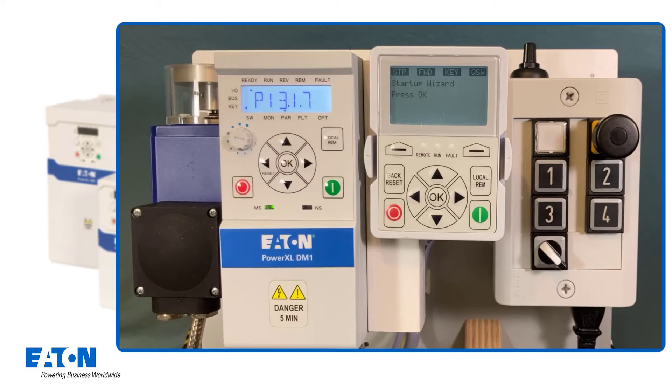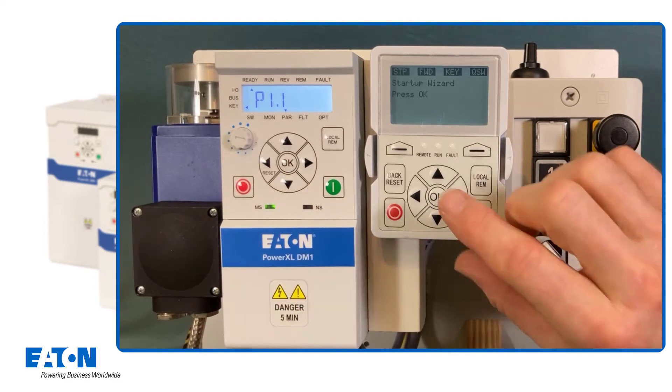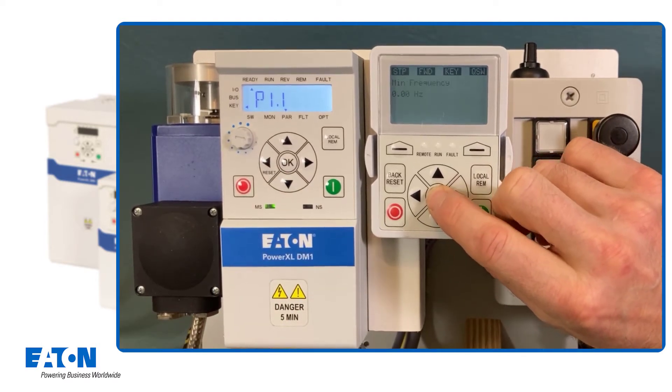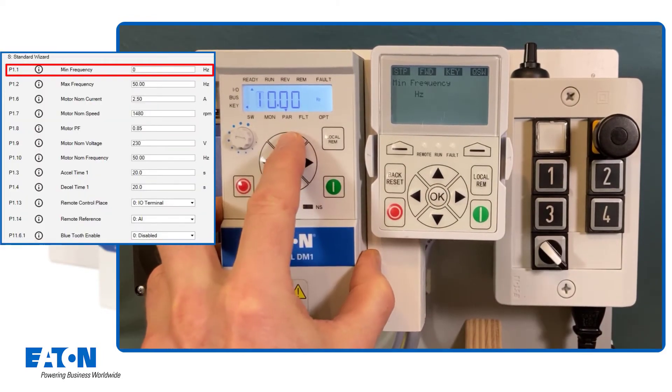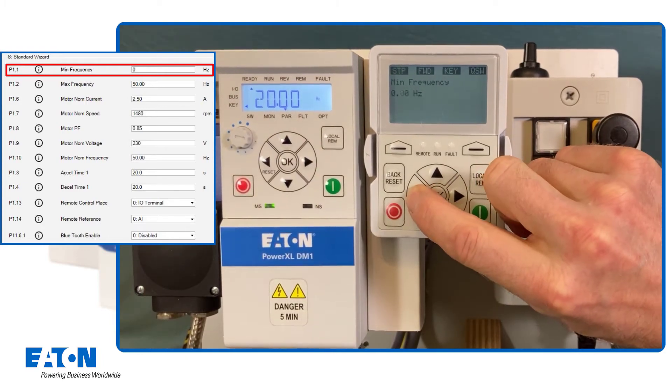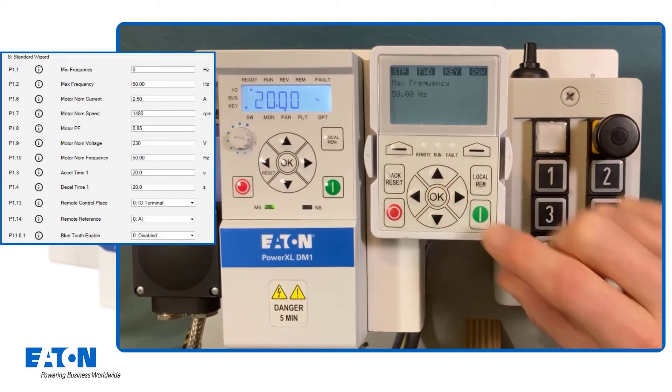On the internal keypad, the first parameter is displayed directly. On the external keypad, the start-up wizard is started with OK. First, you are asked whether the set parameters should be protected against unauthorized changes with a password. In our example, no password is used, so the down arrow key is pressed twice, or on the external unit, switched to the next parameter via OK. The minimum frequency shall be set to 20 Hz. To do this, press the right arrow key and then the left arrow key to set the tens digit to 20, and confirm the entry with OK for both operating units.